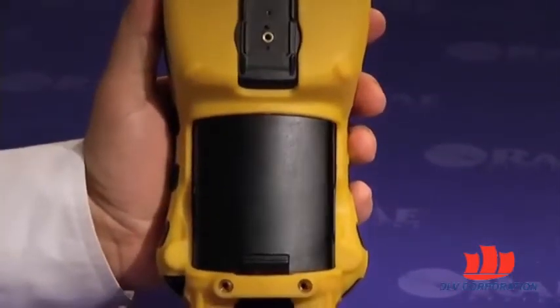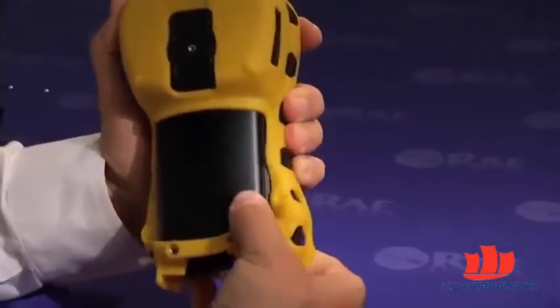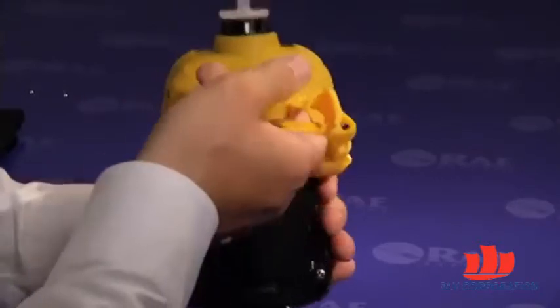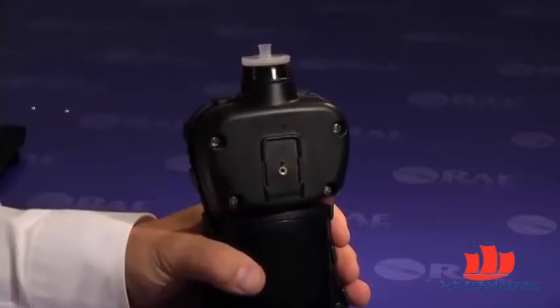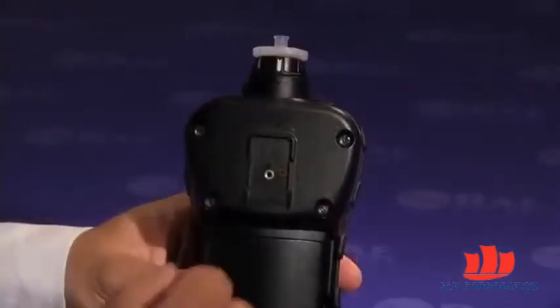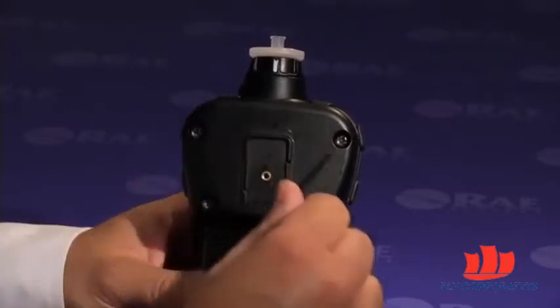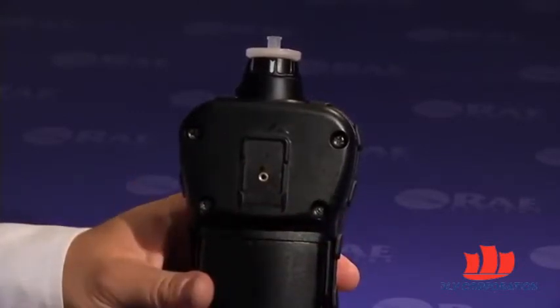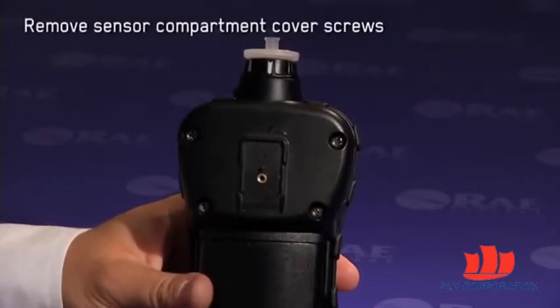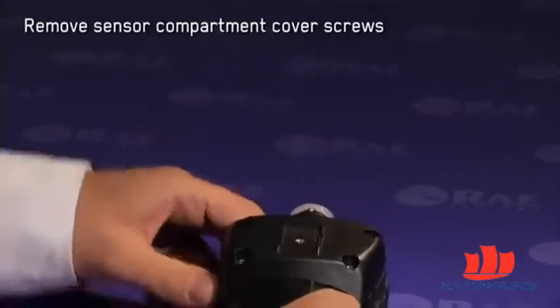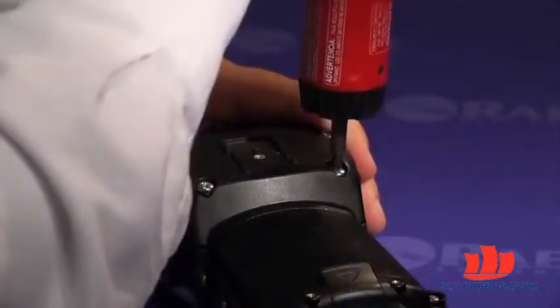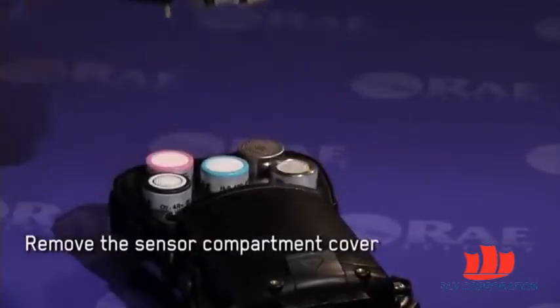Next, remove the rubber boot by pulling on the bottom part of it towards the back, and then gently lift it over the filter and the gas inlet. Set the rubber boot aside. The MultiRAE sensors are located in the sensor compartment at the back of the instrument. The sensor compartment cover is held in place by 4 Phillips screws. So the next step in the sensor replacement process would be to remove these 4 Phillips screws. Next step is to remove the sensor compartment cover.